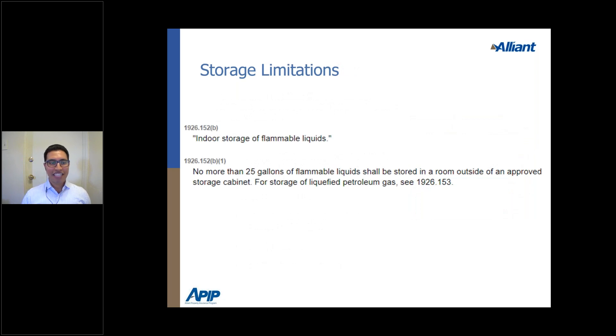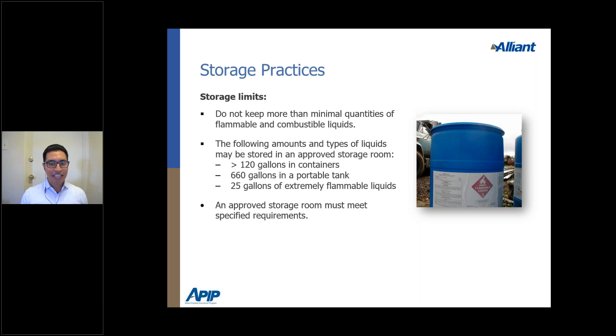There are quantity limitations for flammable liquids, pulled from CalOSHA regulations. No more than 25 gallons of flammable liquids should be stored in a room outside of an approved storage cabinet. OSHA requirements also state: if greater than 120 gallons, must be in containers; 660 gallons in a portable tank; and up to 25 gallons of flammable liquids in approved storage rooms.